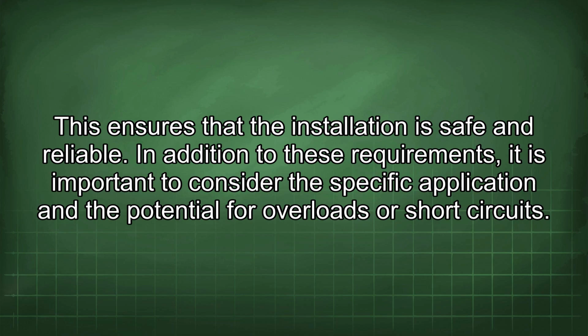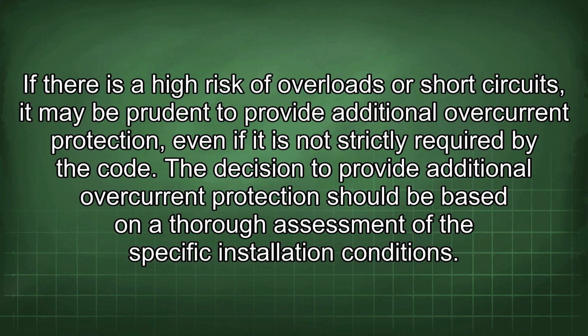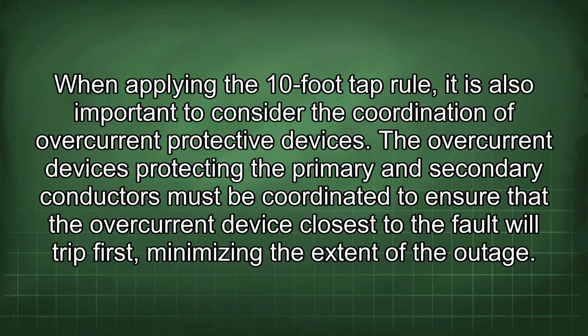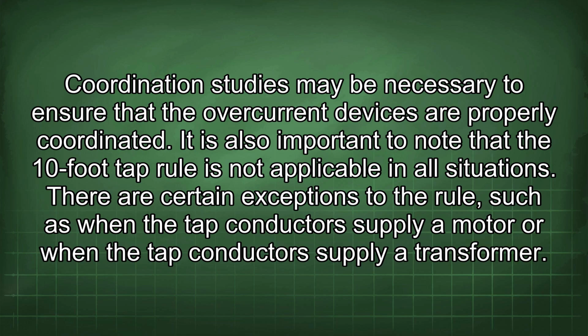In addition to these requirements, it is important to consider the specific application and the potential for overloads or short circuits. If there is a high risk of overloads or short circuits, it may be prudent to provide additional overcurrent protection, even if it is not strictly required by the code. The decision to provide additional overcurrent protection should be based on a thorough assessment of the specific installation conditions. When applying the 10-foot tap rule, it is also important to consider the coordination of overcurrent protective devices. The overcurrent devices protecting the primary and secondary conductors must be coordinated to ensure that the overcurrent device closest to the fault will trip first, minimizing the extent of the outage. Coordination studies may be necessary to ensure that the overcurrent devices are properly coordinated.